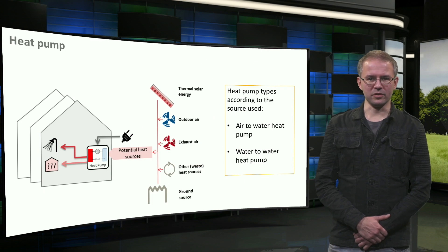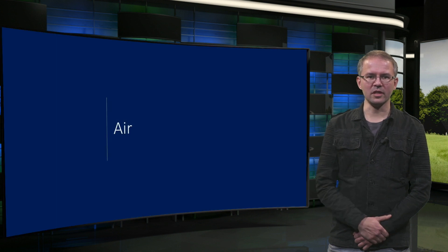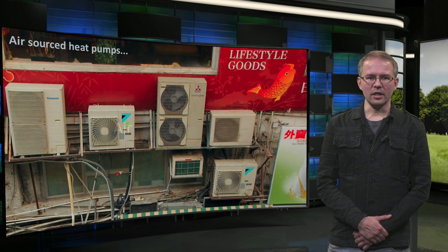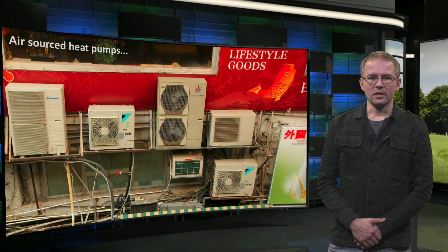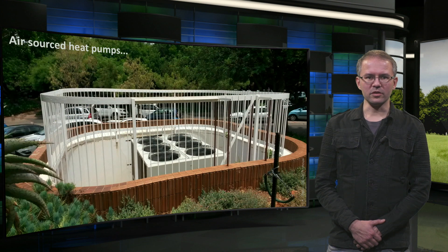We will now move on to the sources. Air will be the most familiar environmental source of energy, especially for cooling. In a previous lecture you have learned about air conditioning or AC units. These are also known as air-sourced heat pumps because they use the outside air as a heat sink. They can also be used in reverse to heat up your building. Compared to the other sources, air-sourced heat pumps are however the noisiest and least efficient. They will use a lot more electricity for the same amount of heat or cold and are therefore more expensive when used.